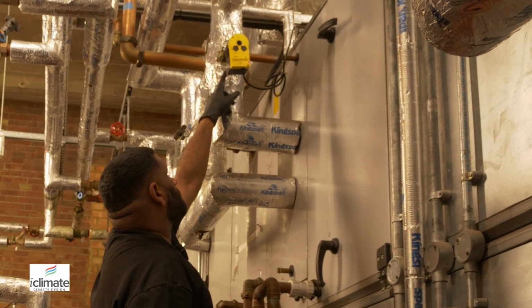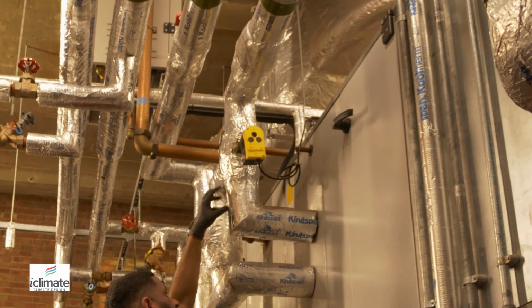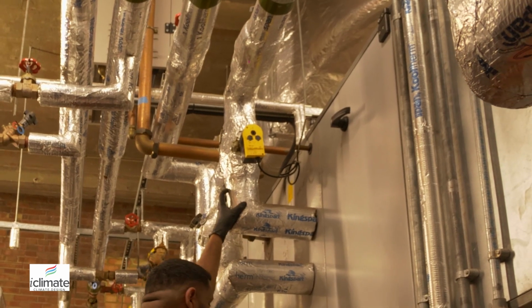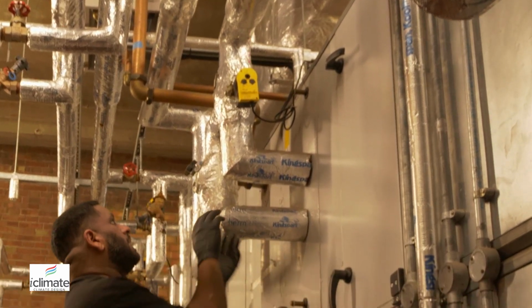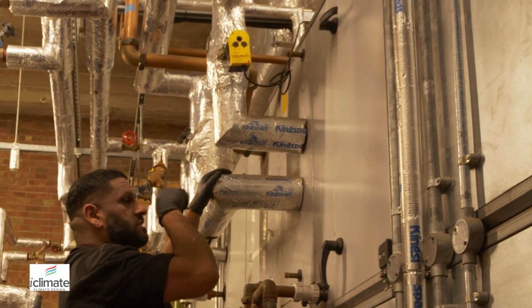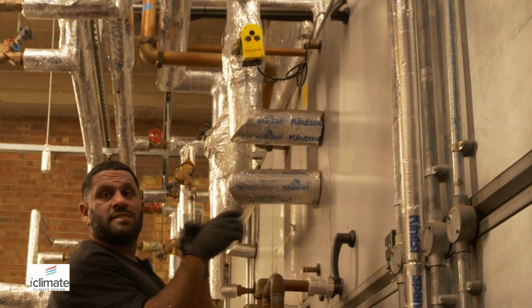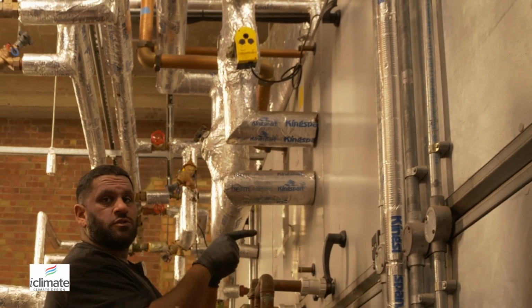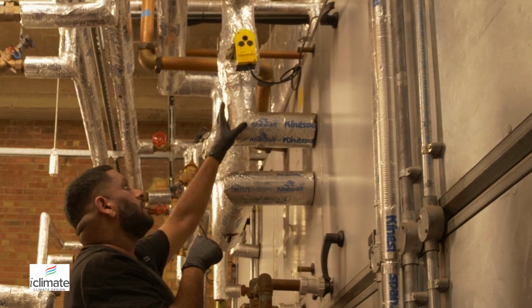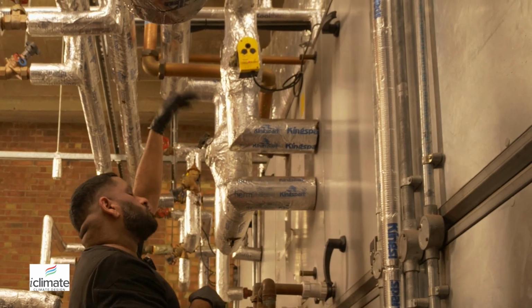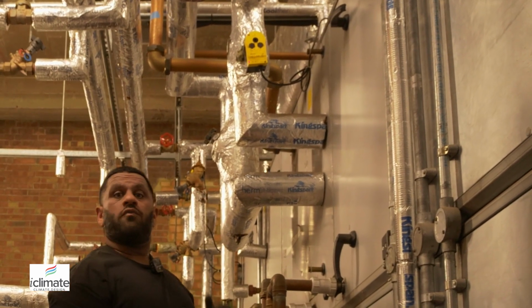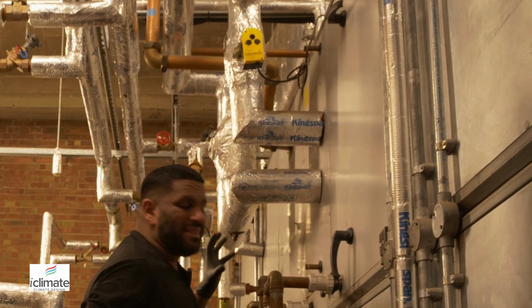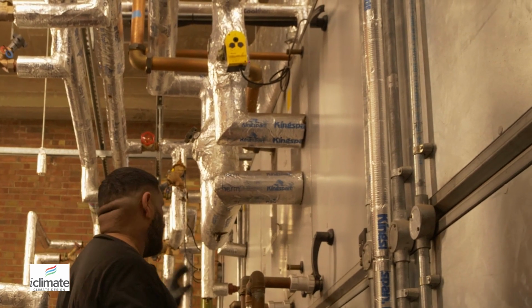This is what I call a 3-port valve, right, which sits on the return. Every time you see a valve, it's on the back of a heat exchanger, and then the valve is controlled by the BMS, or if it's a standalone air handler that has temperature sensor settings set onto it for the specific heater set point, it will then control the operation and the flow of hot water or chilled water within that specific battery to provide a perfect environment.